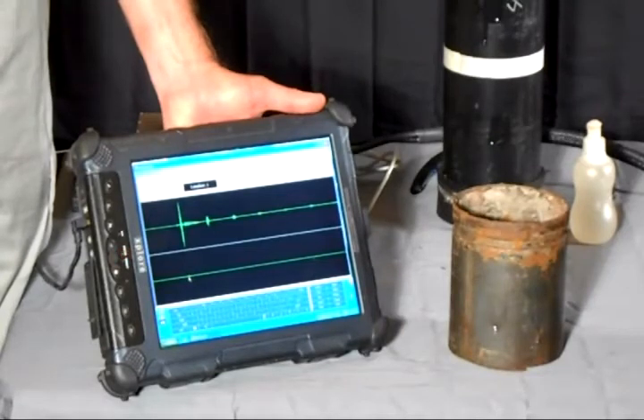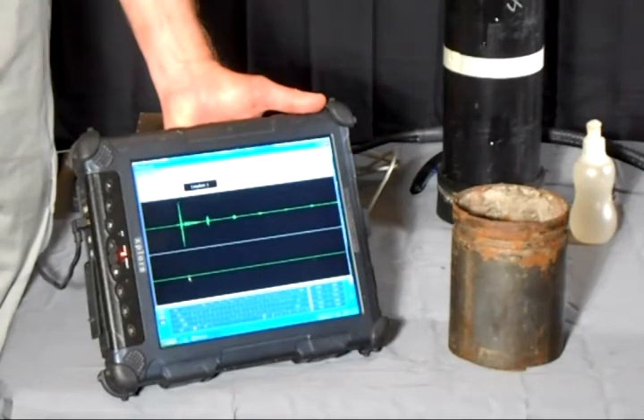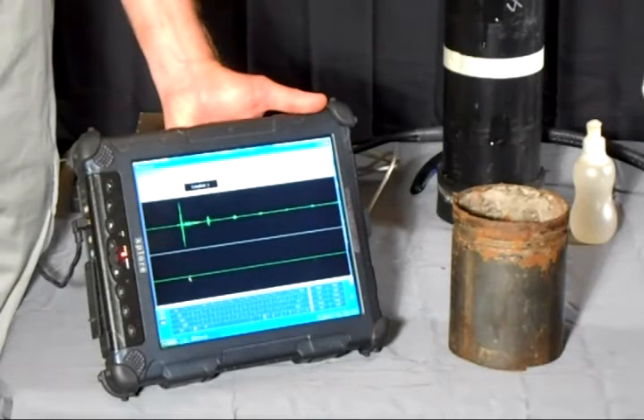So when we're out testing in the field, we would then follow up with the thickness gauge in those areas and really hunt around and look for the absolute worst spots to tell you how bad the worst areas are within your system. It's a very effective and accurate way to determine corrosion issues inside your piping systems.